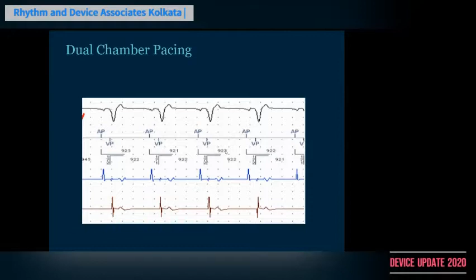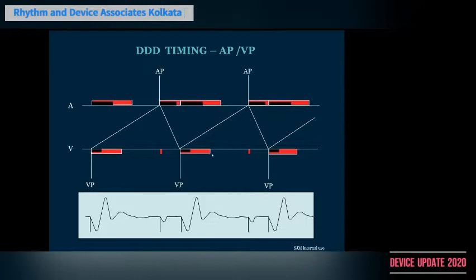So what happens in AP and VP? Simply put, an atrial pacing spike occurs, 2 refractory periods are initiated in the atrial chamber, and then a ventricular pacing spike occurs, which leads to initiation of 2 different refractory periods in the atrial chamber as well as in the ventricular chamber. The black one is the blanking and the red one is the refractory period. So in the atrial chamber, you have 2 different blanking and refractory periods, before the ventricular event and after. And in the ventricular chamber, you have 1 blanking period and refractory period which occur after the ventricular paced event. So this is how dual chamber APVP goes on.